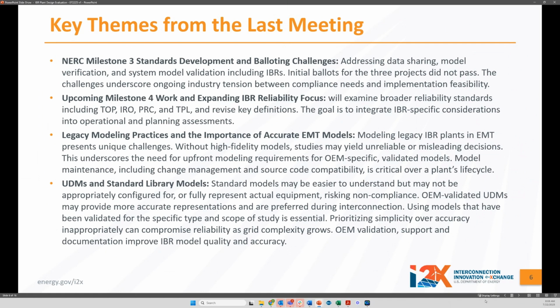They're mandated to be used in interconnection-wide models through the FERC 901 process. But having OEM validated, accurate, site-specific, user-defined models, with much more detailed controls represented, whether in positive sequence simulations or in EMT, is generally preferred and recommended, particularly for interconnection studies or local reliability studies. These generally yield better outcomes, although they're sometimes more difficult to understand or use, and often require OEM engagement, validation, and support documentation. So it's really a balance and trade-off - some uses for some models, other uses for other models - and understanding the specific type of model and scope of the study is necessary.